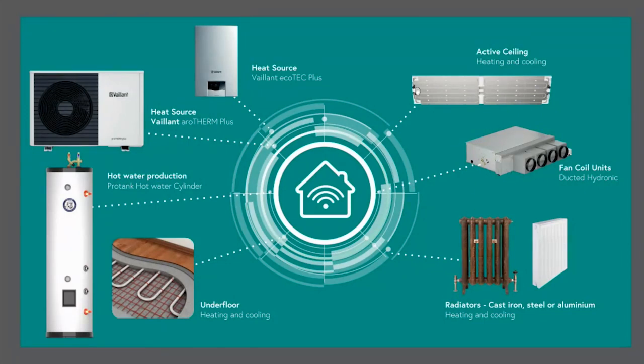And then some other products we've added to our range in recent years. We do ducted fan coils, and so these are hydronic units, so they will take hot or cold water, and they can be set up different ways. They can be set up ducted and ductless. So a ducted system has a plenum on it, like is shown there, where you connect flexible duct on. So that would turn that system into a ducted system, a lot like the air conditioning heat pump systems that are available on the market, but it's run by water, not refrigerant.